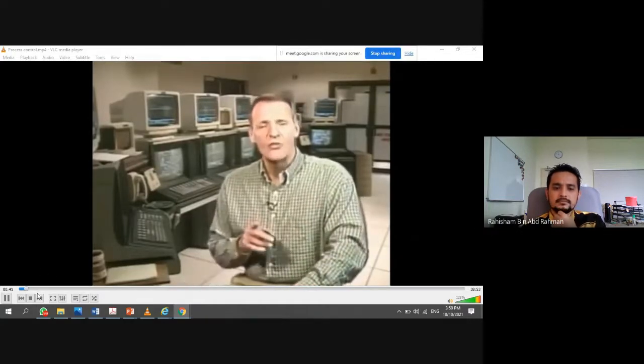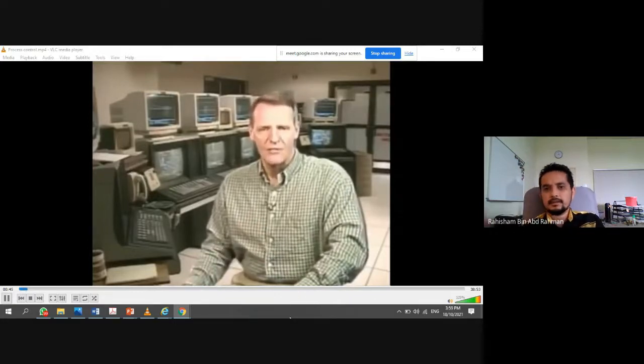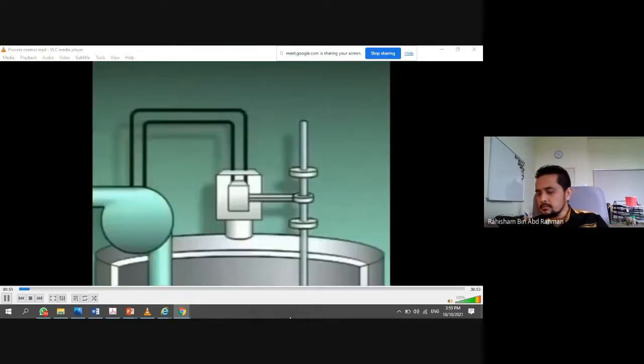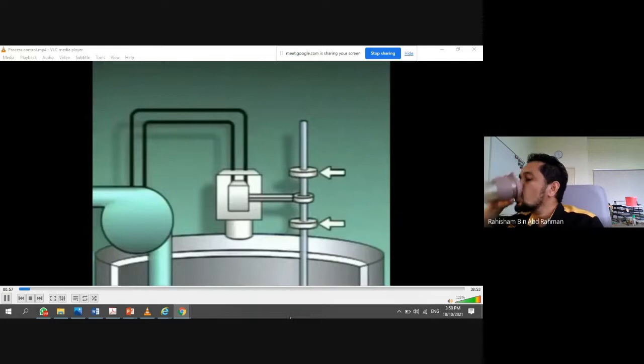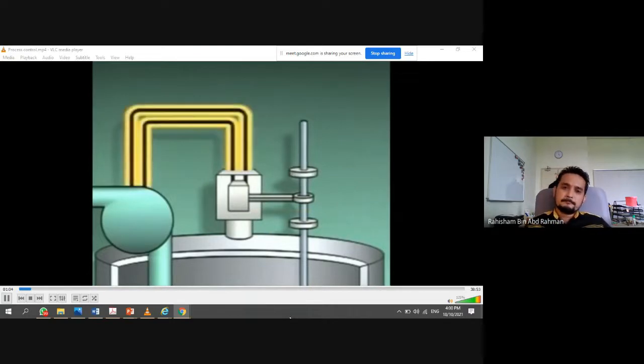To see how two-position control works, let's look at an illustration of a sump pump arrangement. In this system, a pump draws water out of a pit or sump. A float with a rod is the sensing element in the system. The float rod has two collars, which serve as stops for a linkage that connects the rod to a switch. It's part of an electrical circuit that starts and stops the sump pump motor.